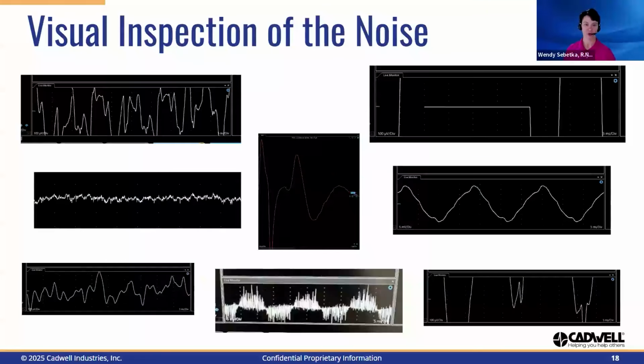Visual inspection of the noise will allow you to make some mental notes of the details of the waveform pattern. Does it look spiky? Is it consistent? Maybe it's disorganized. Is the baseline straight, flat, or fatter than I'm used to? Visual inspection of the noise can be helpful in giving you a direction to work with. In most situations, your live monitor is going to be your friend and will provide you with real-time feedback as to whether or not your troubleshooting techniques are successful.